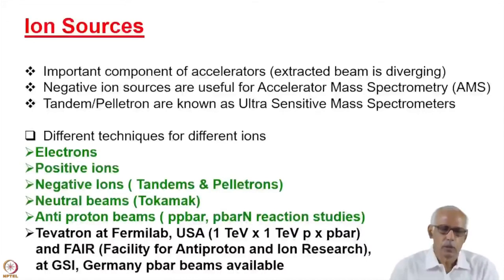This is, as I said, the most important component of any accelerator. In fact, 80% of downtime in any accelerator is because of malfunctioning of ion source. Therefore, it has to be properly designed, built, and tested before it is installed in the accelerator.